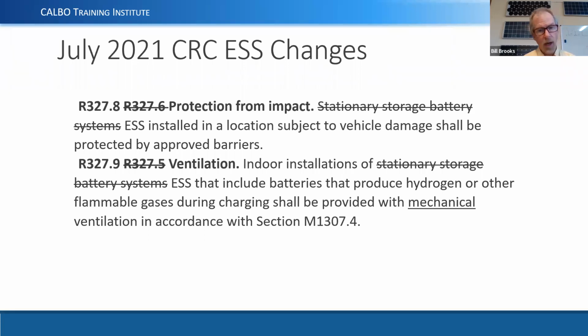Ventilation requirements from day one when we're talking about battery systems have always been about normal charging of flooded lead acid batteries that have a propensity to give off hydrogen when they're being charged hard. And that hydrogen, if it is collected in a box that's sealed, can establish an explosive mixture. So again, this is a section of the code we really don't have to worry about right now, because we're using lithium-ion batteries in our ESS, and we're starting to use valve-regulated lead acid batteries in our ESS as well that are UL 9540, neither of which require ventilation.